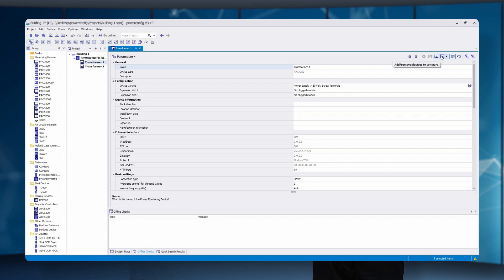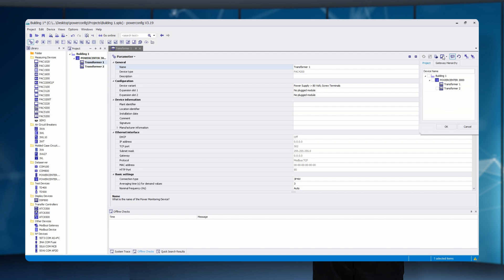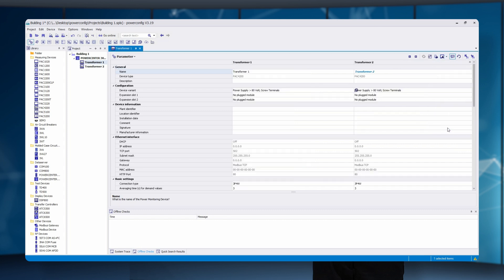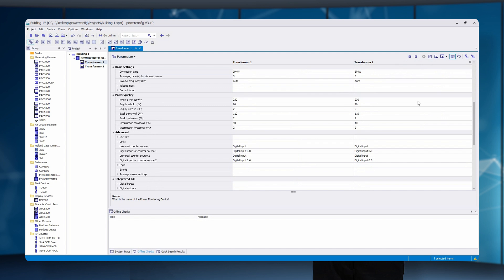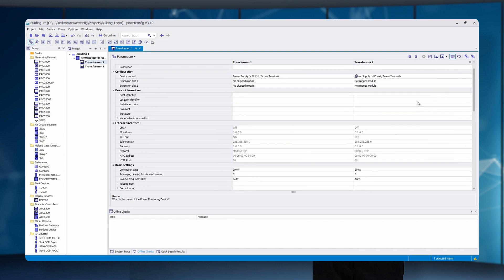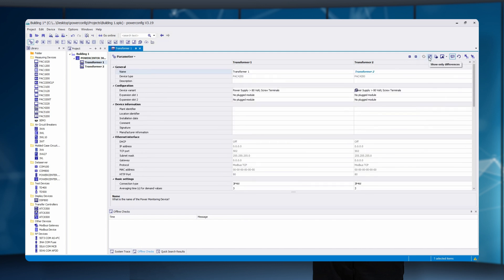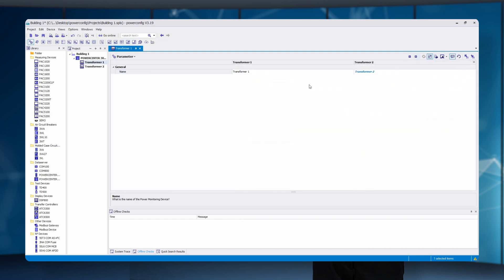The second one is the device comparison. If one subsystem works and the other does not, although they are similar, those devices can be compared with each other — for example, transformer1 and transformer2. By selecting the filter function, only the differences can be shown. In this example, the difference is in the name. This function is especially helpful during commissioning or troubleshooting.